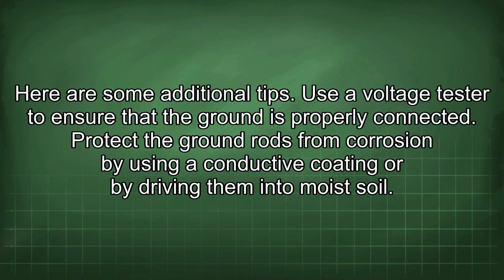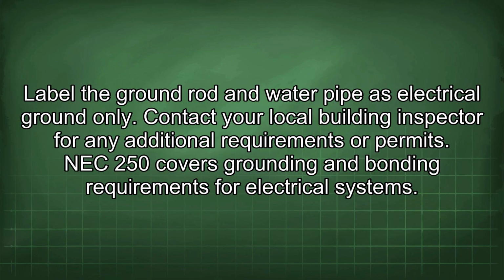Here are some additional tips. Use a voltage tester to ensure that the ground is properly connected. Protect the ground rods from corrosion by using a conductive coating or by driving them into moist soil. Label the ground rod and water pipe as electrical ground only. Contact your local building inspector for any additional requirements or permits.